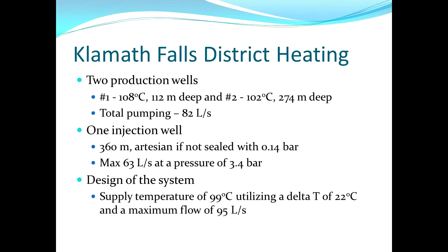Klamath Falls has two production wells, 112 meters and 274 meters. One's 108 degrees C and the other's 102 degrees C. When they're pumping the water up, they have to make sure it stays under pressure, because if it stays under pressure it stays water. If they lose a little bit of pressure, it'll flash to steam, and that two-phase water isn't always very good for their system, so they try to keep it pressurized.